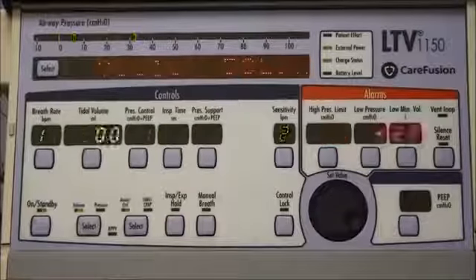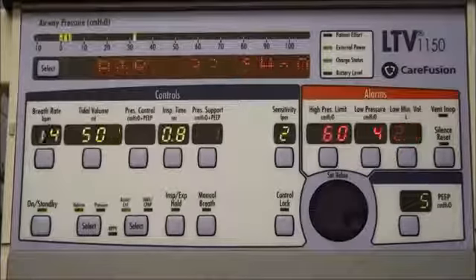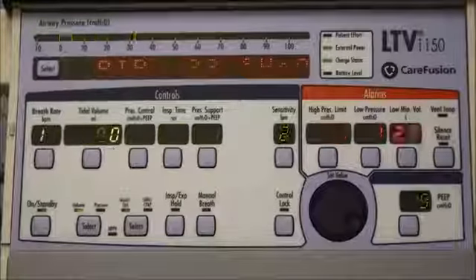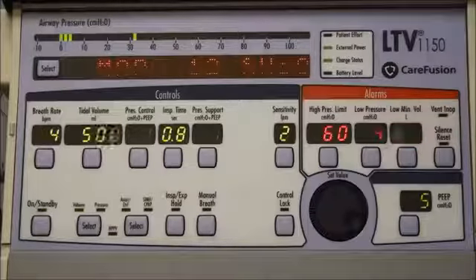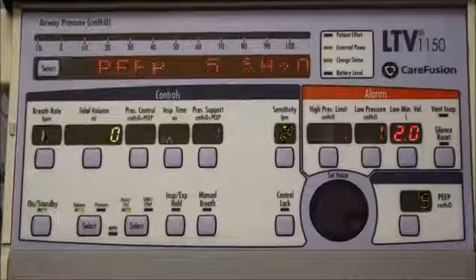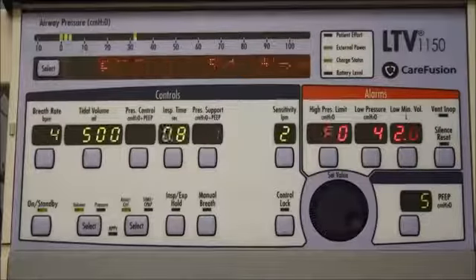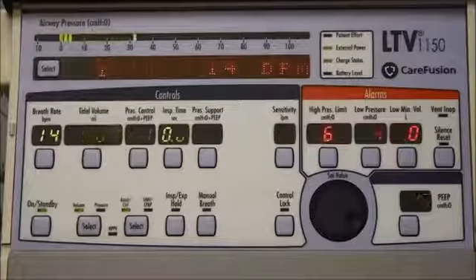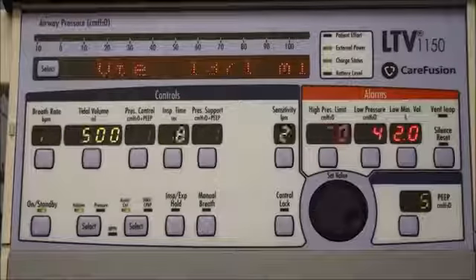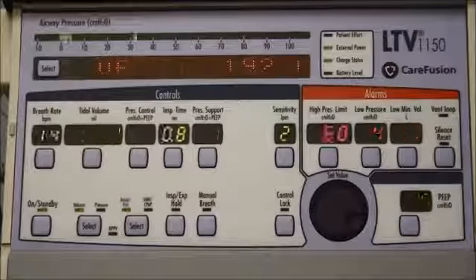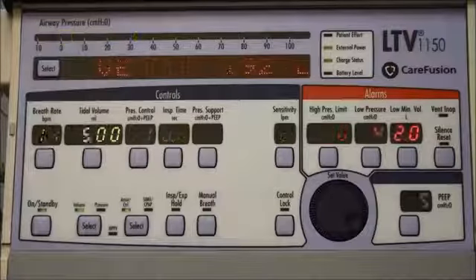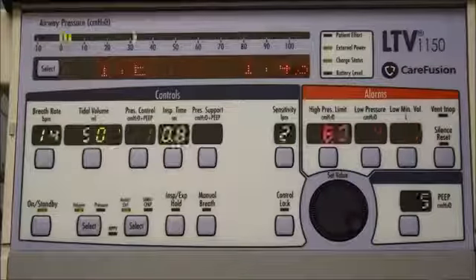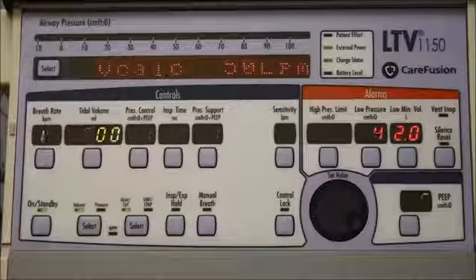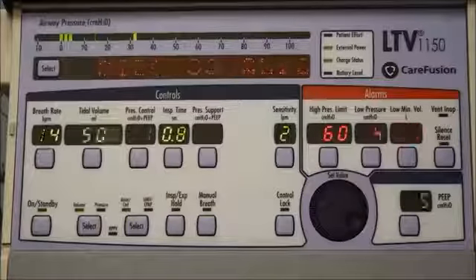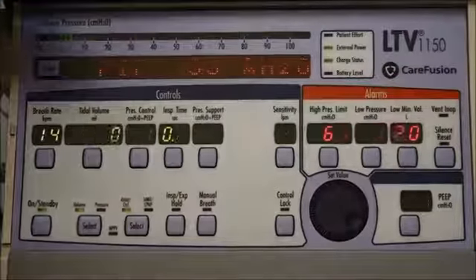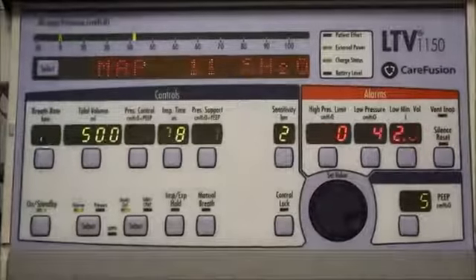And what you would need to do is figure out why those pressures are up above 60 and solve that problem, whether it's water in the tubing or patient suctioning or something along those lines. Low pressure would be some sort of leak or disconnect in the patient's circuit. So whatever you have your low pressure set at, if the pressure would go below that, then you would get a low pressure alarm. So I'm going to demonstrate what that would look like.